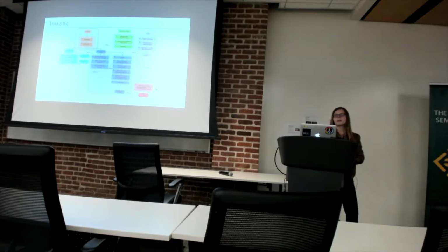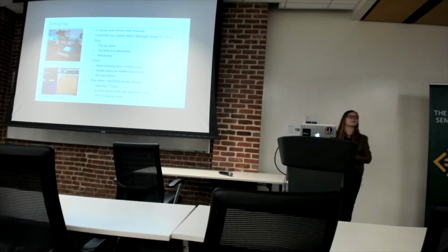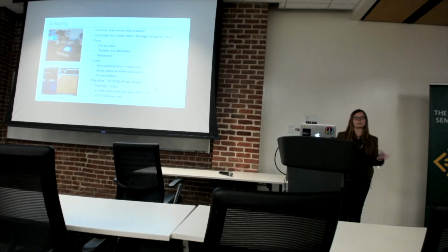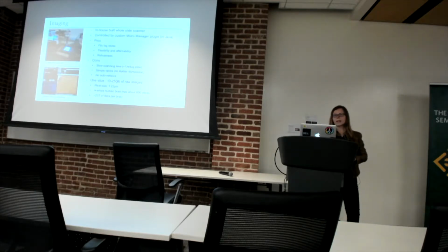So the first thing was developing an imaging platform for those slides. As I said, the slide is too big, it's 6 by 5 inches, and it doesn't fit a regular microscope. The microscope stages are way smaller than that. So we developed an in-house scanner, which is a prototype. It doesn't look that glorious, but it works well. It has scanned more than 500 slides by now. We also developed the software, and it was very cost-effective for the lab. It's way cheaper than a commercial scanner.